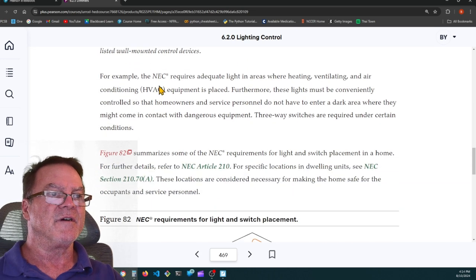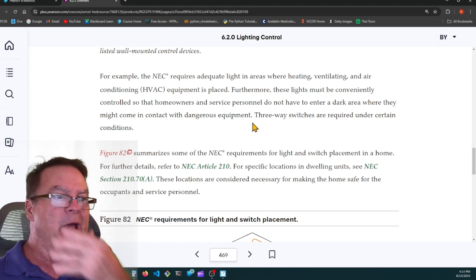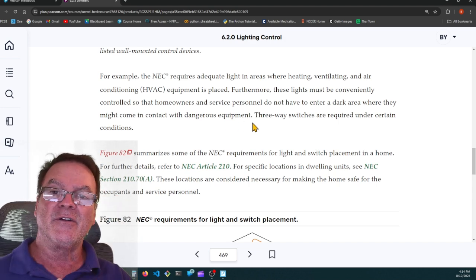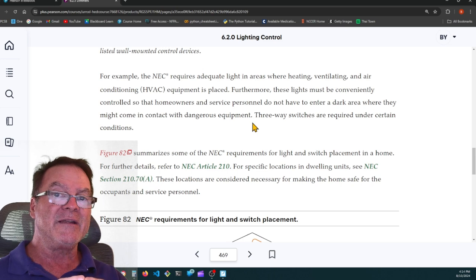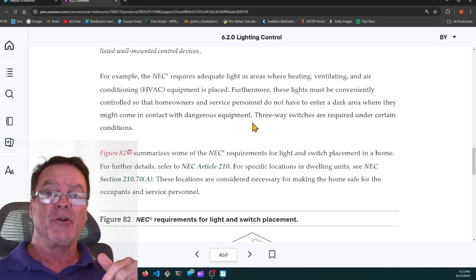And so this says, for example, the NEC requires adequate light in areas where heating, ventilating, and air conditioning equipment is placed. Furthermore, these lights must be conveniently controlled so that the homeowner and service personnel do not have to enter a dark area where they might come in contact with dangerous equipment. So if you have an air handler in your attic, you have to have a light by the air handler in your attic controlled by a switch that's at the scuttle hole.